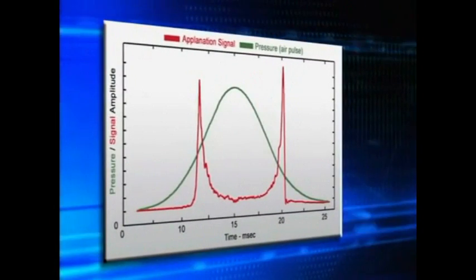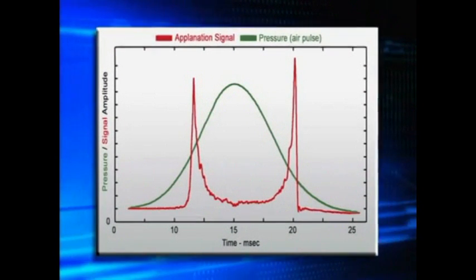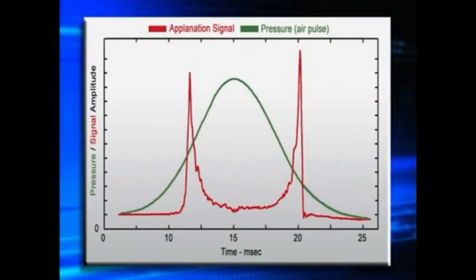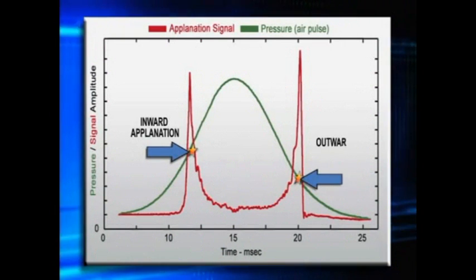The entire measurement process takes approximately 20 milliseconds. The process results in a measurement signal similar to this one. The internal pressure transducer records the pressure required to flatten the cornea at the moment of each applanation event.